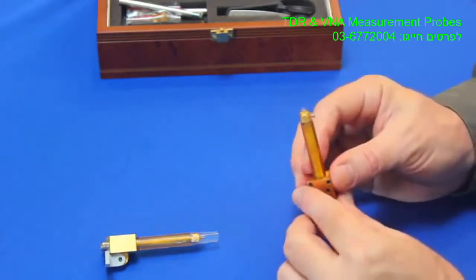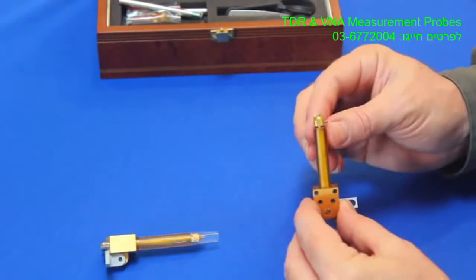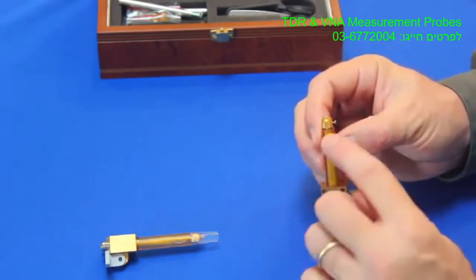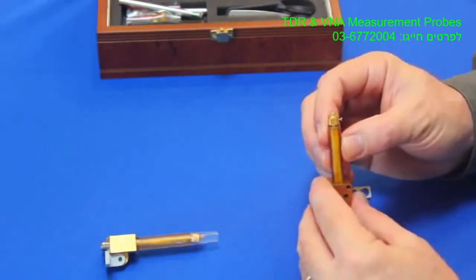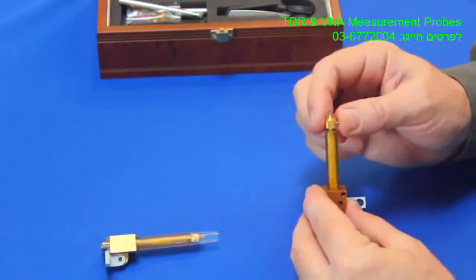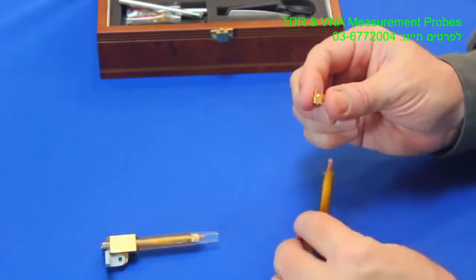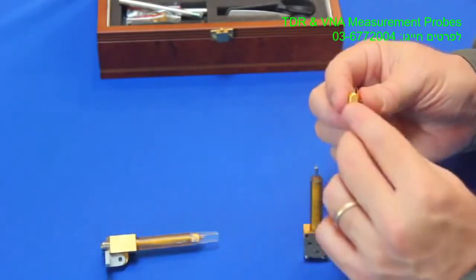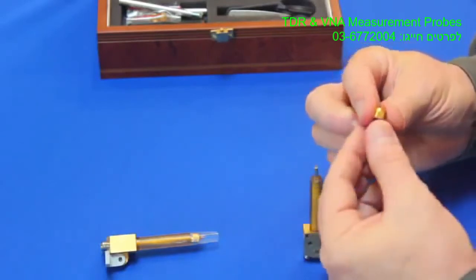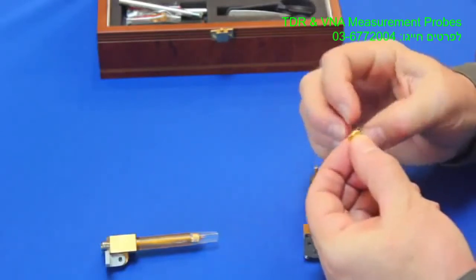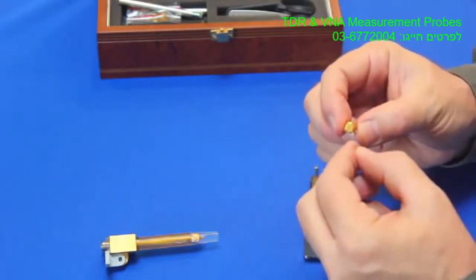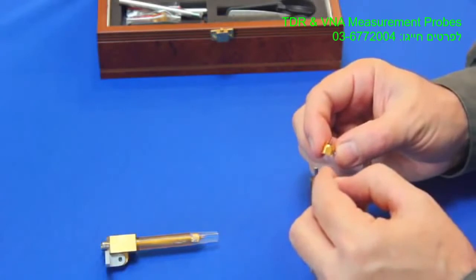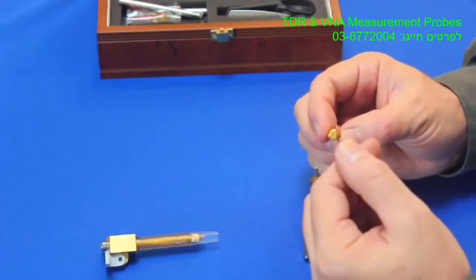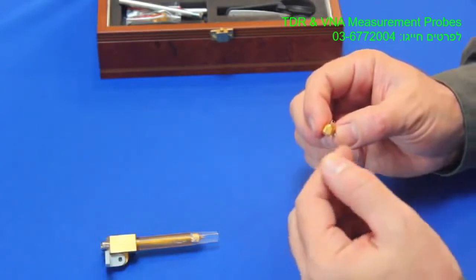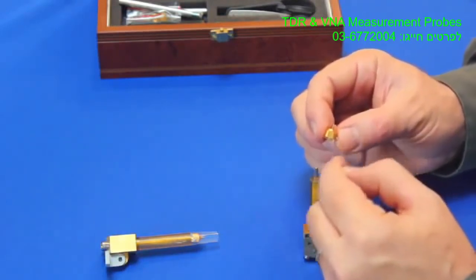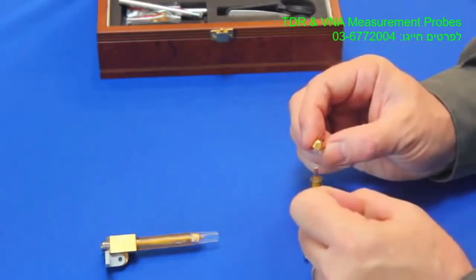On the probe end, we have a new ground collar assembly that has 3 pins in it that are compliant, that is, they're spring loaded and can be removed. By pushing the pins from the front side to the back side, we're able to configure the ground configuration in relationship to the signal pins. So you could have ground, signal, ground, or any combination of that just by removing one of these pins and then applying it back onto where it was assembled.